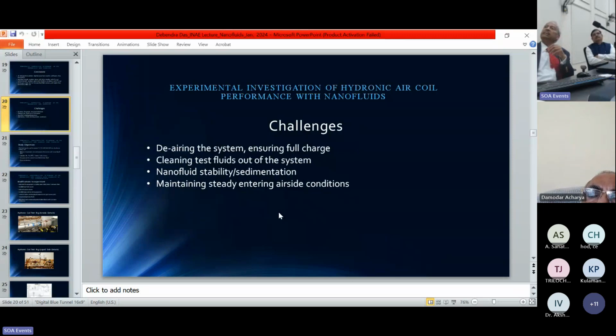Maintaining a steady entering air side condition was also difficult, because our experimental setup was near some doors, and people accessing those doors would often open them. In the cold climate of Alaska, once the door opened, cold air at maybe 4 degrees Celsius would come in, and the air side temperature would immediately fluctuate. We wanted to do the experiment at a very controlled, constant air side temperature so we could predict the performance of the air coil very well.